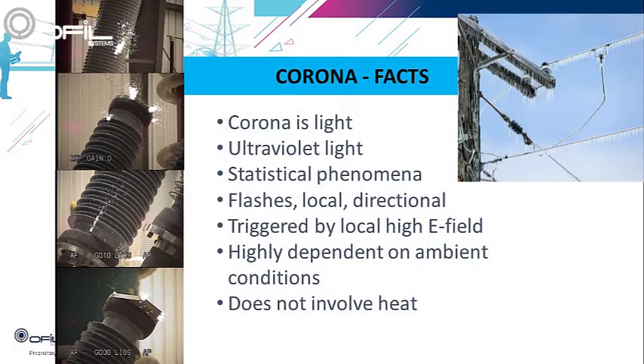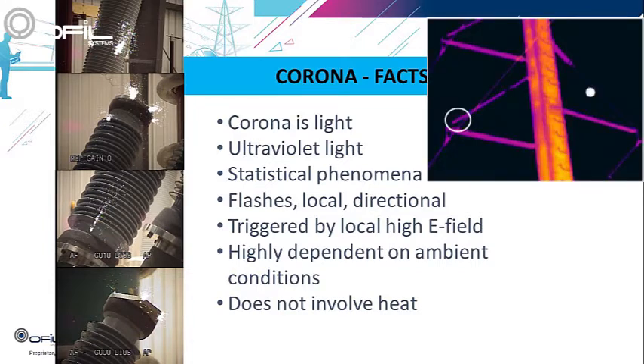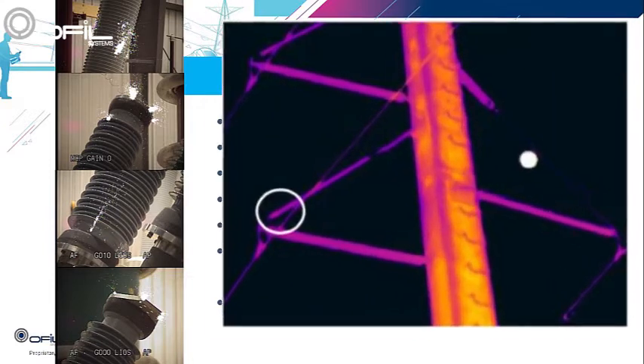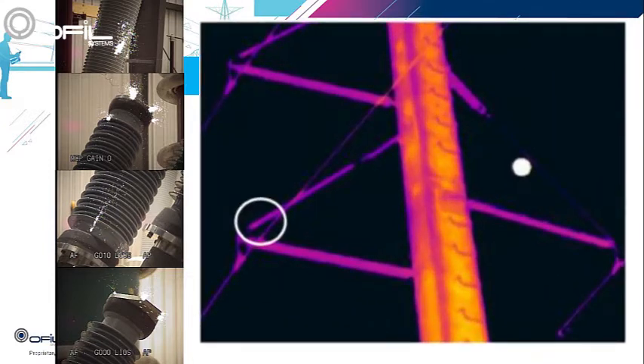Corona is highly dependent on ambient conditions. Temperature, humidity, and air pressure affect the acceleration and mobility of free electrons to collide with neutral molecules and excite them. It may therefore happen that a strong corona becomes extinct under certain ambient conditions. Corona does not dissipate heat, or very low heat, and therefore will not be depicted by thermal cameras — making IR cameras inefficient for corona detection.